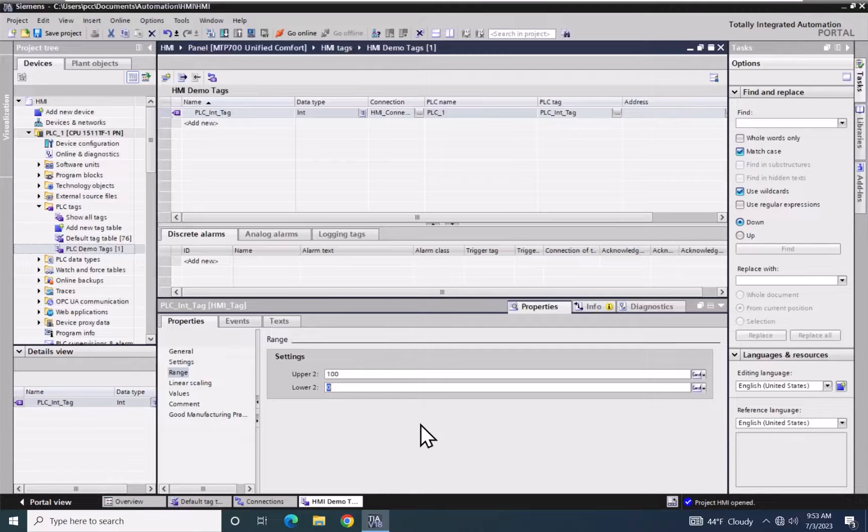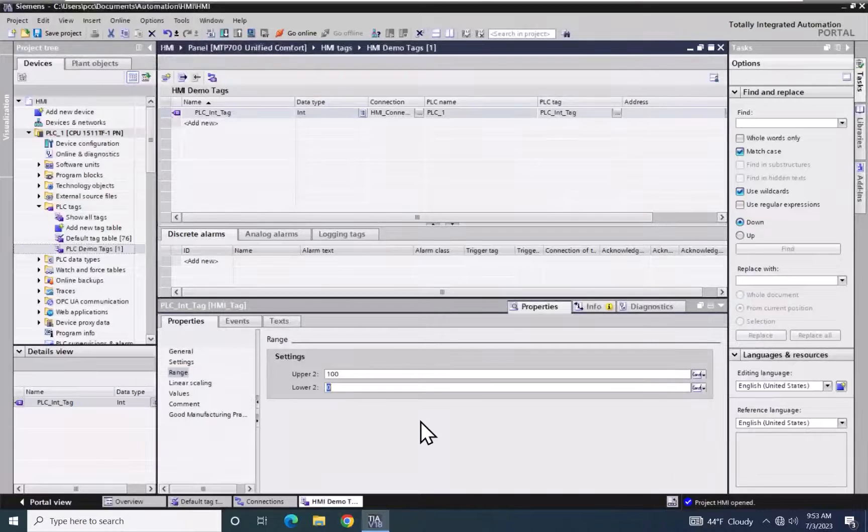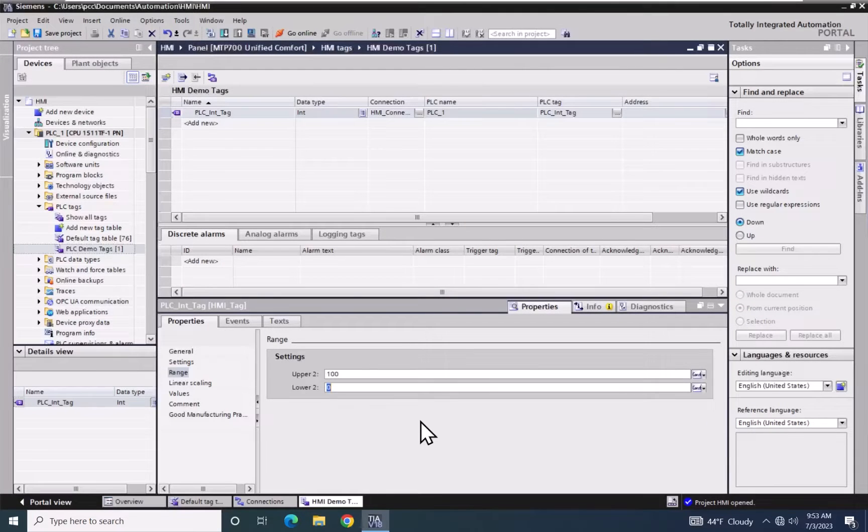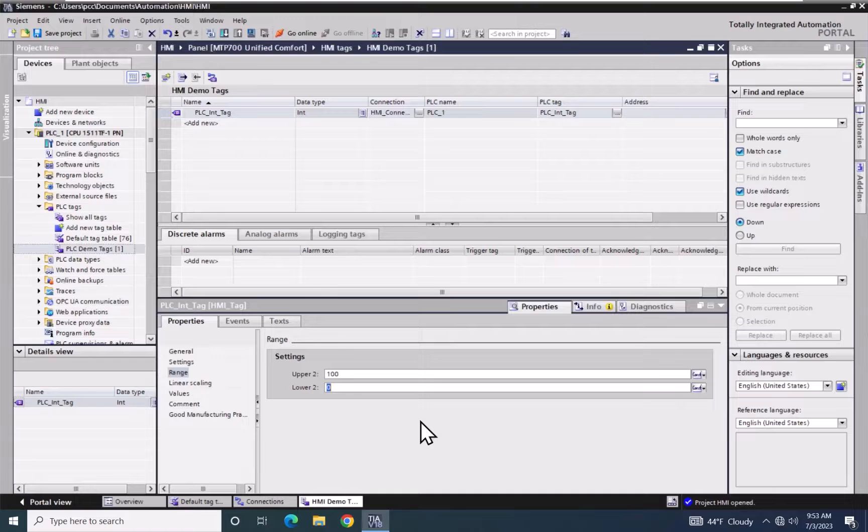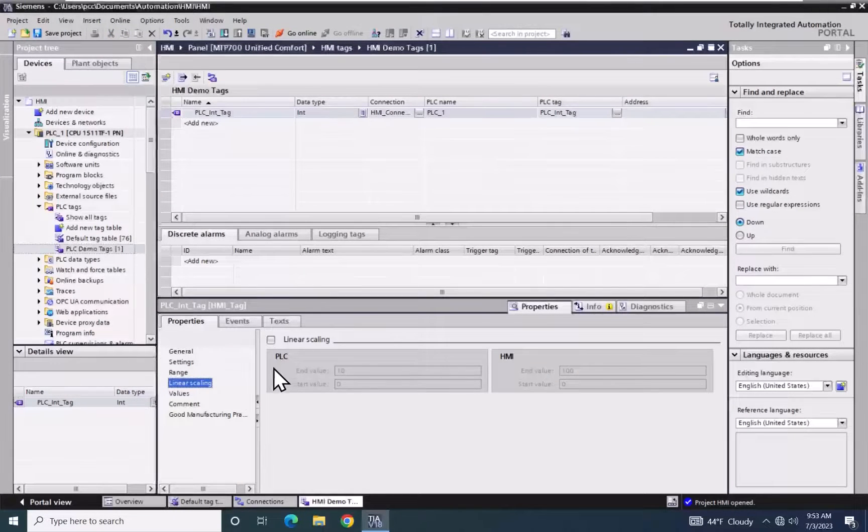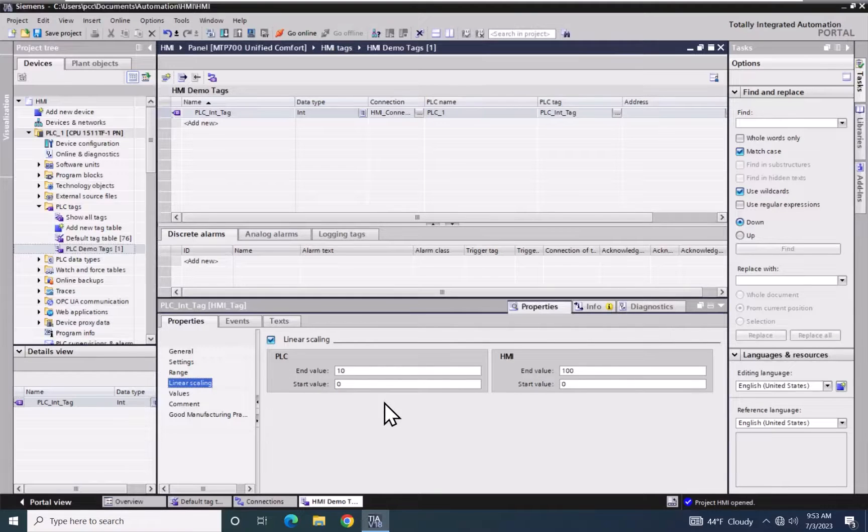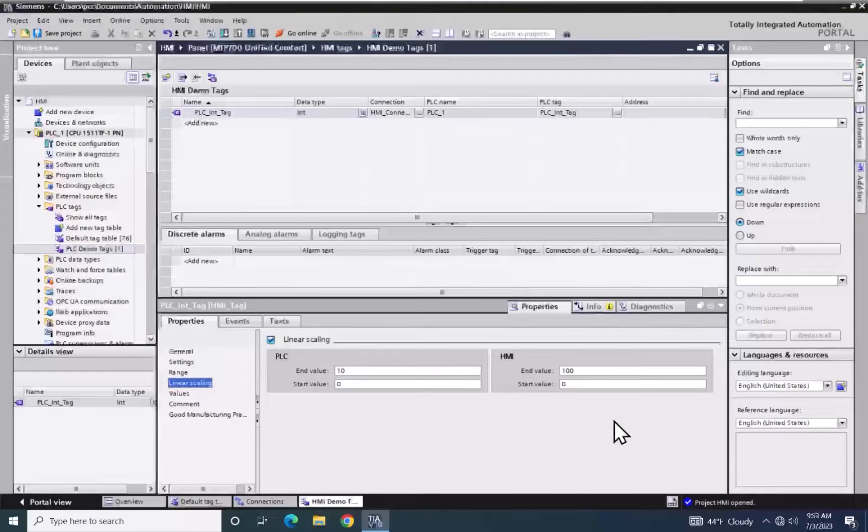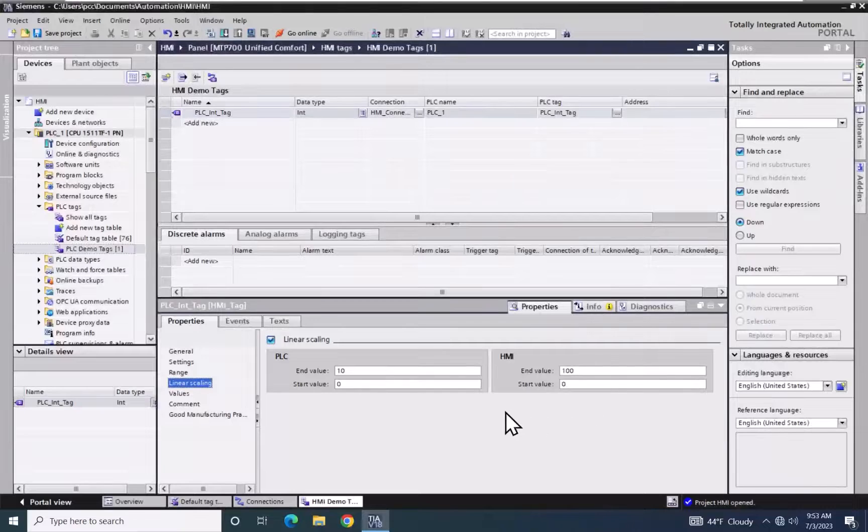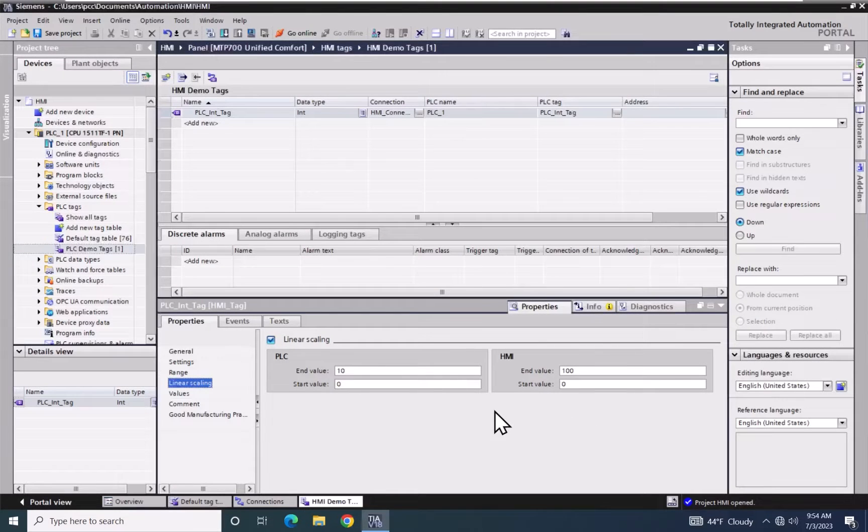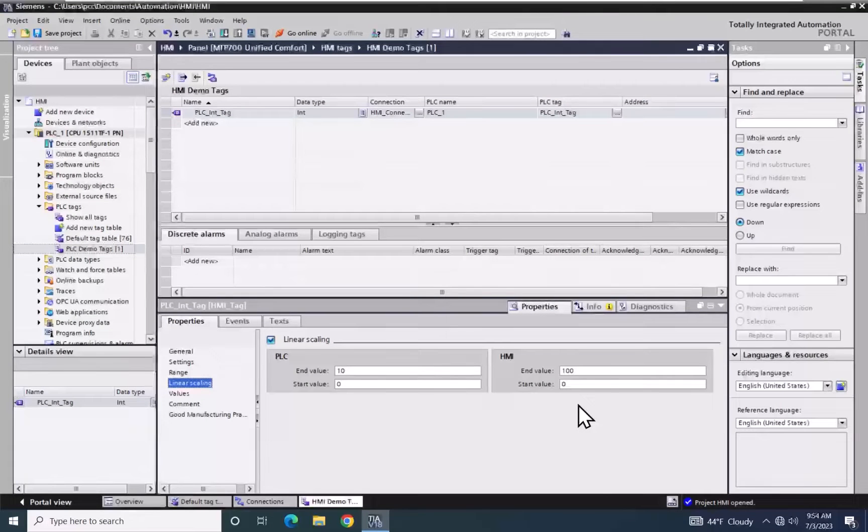So when I set a range between 0 and 100 on the HMI during runtime, the operator will only be able to enter in a value between 0 and 100. There is also linear scaling. If linear scaling is enabled, you can scale the value in the PLC to HMI units. So in this case, it would be like multiplying the value in the PLC by 10 and displaying that scaled value on the HMI.